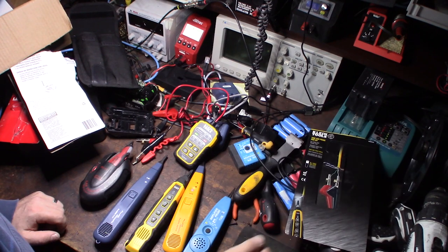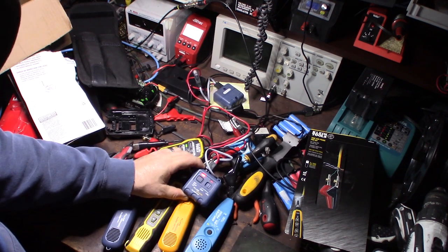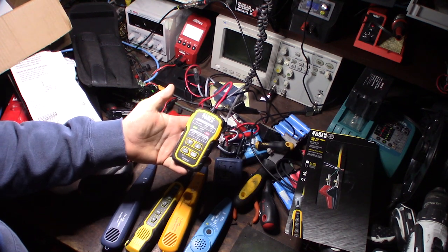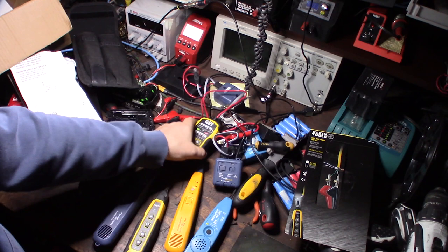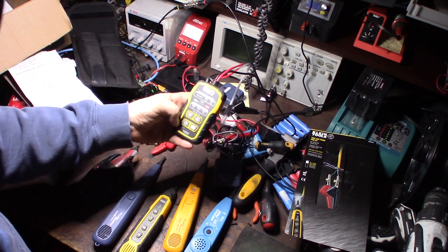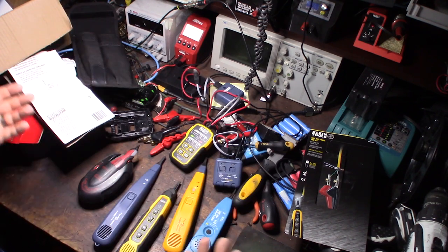The other annoying feature — and this is the actual deal breaker for me, the thing that frustrated me the most — is that this Fluke toner will stay on forever until you turn it off, and that's what I like. But at least ten times using the Klein, it would auto shut itself off. There's an auto shut-off timer to save the battery. I'm on the other side of the building trying to find the wire in the bundle, and this thing has auto shut off on me. I spent fifteen minutes in a big bundle of wires trying to figure out where the wire was, spinning my wheels, because the toner had shut itself off on the other side. And there's no way to disable the auto shut-off timer.